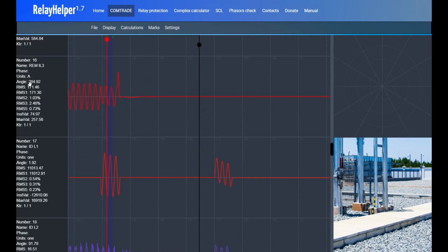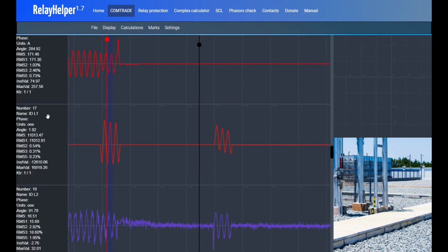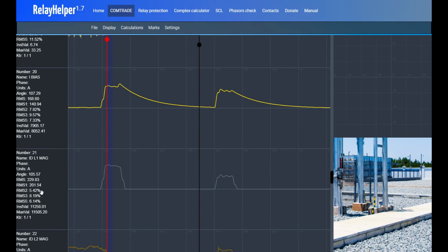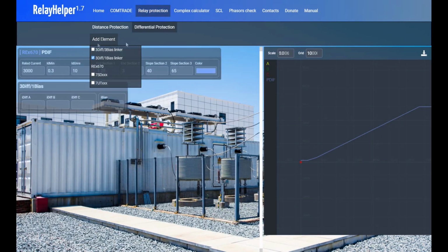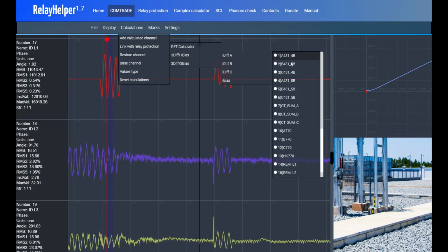But let's use this as an example of one feature of our linkers. They can also be used with these alternating instantaneous values. If any linked channel is alternating, the linker calculates the signal magnitude and uses it. The only issue is the device looks into the past, or to the left of the cursor, but all our algorithms look to the right of the cursor.